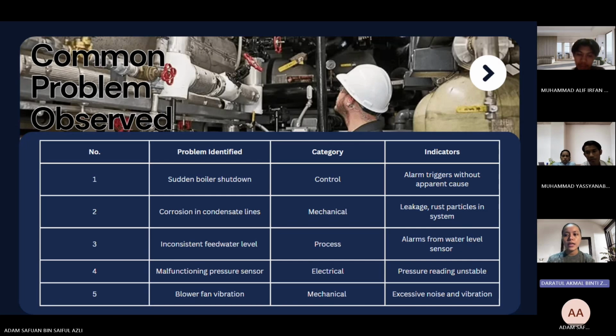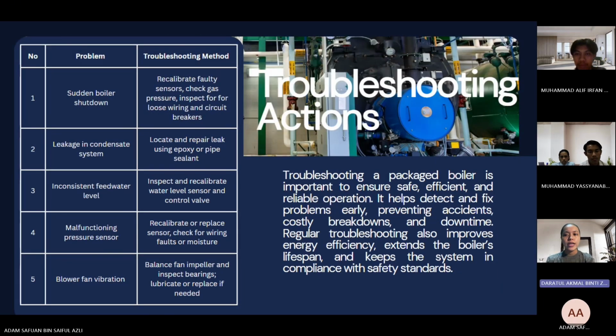Malfunction of the pressure sensor is categorized under electrical fault. The pressure reading tends to be unstable or erratic. Last but not least, we have blower fan vibration, a mechanical issue that is easy to detect due to excessive noise and vibration. To address these issues, we implemented several troubleshooting actions to restore boiler performance and reliability.